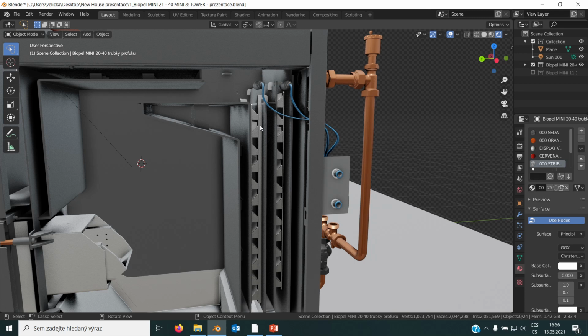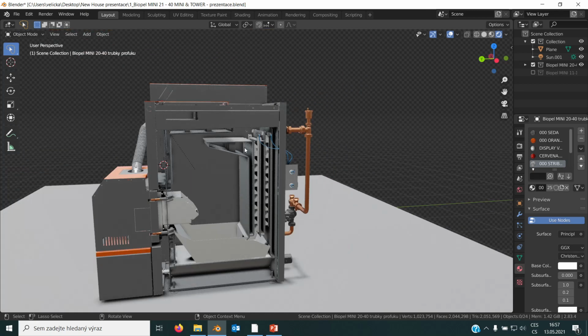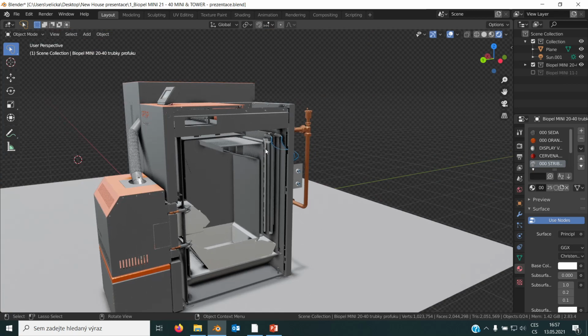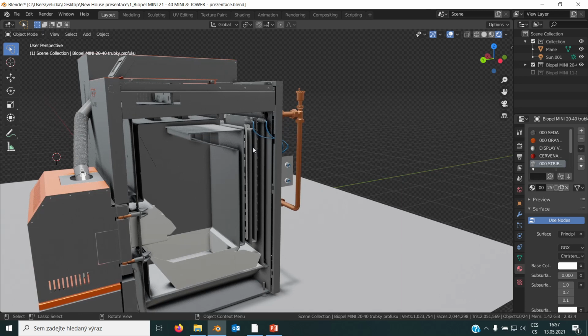Of course, in the manual there is a section about cleaning, and it is written there that customers should check the burner. He should check the heat exchanger at least once a month to make sure that everything is clean. Of course, if the cleaning of the boiler is not efficient enough, then the question is whether the combustion and quality of the pellets are good, or you can even make the cleaning intervals more often to make sure that it cleans properly. But because of the small size of the boiler, the cleaning with 8 bar pressure is really efficient, and there is no moving mechanism inside which could be damaged by heat. It's just air going to the boiler.